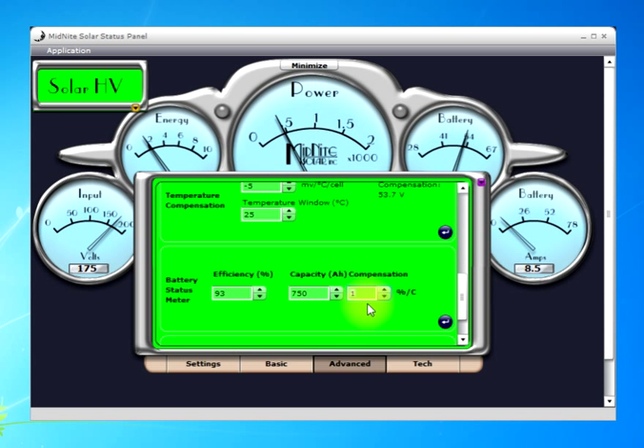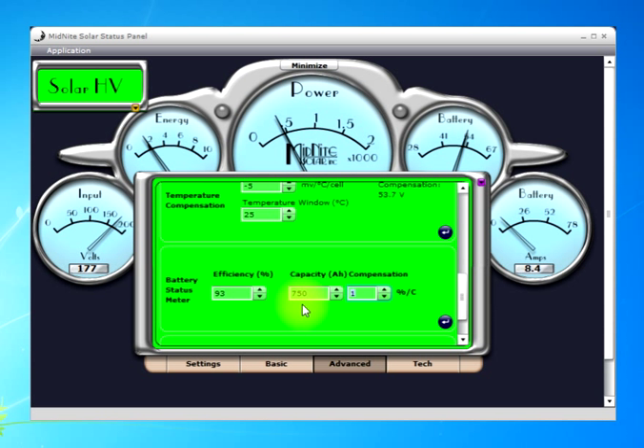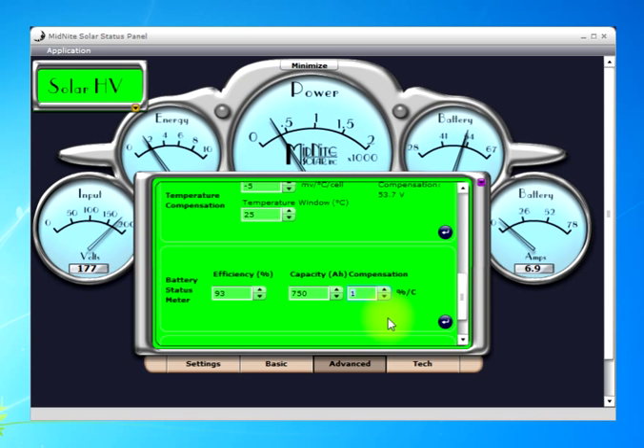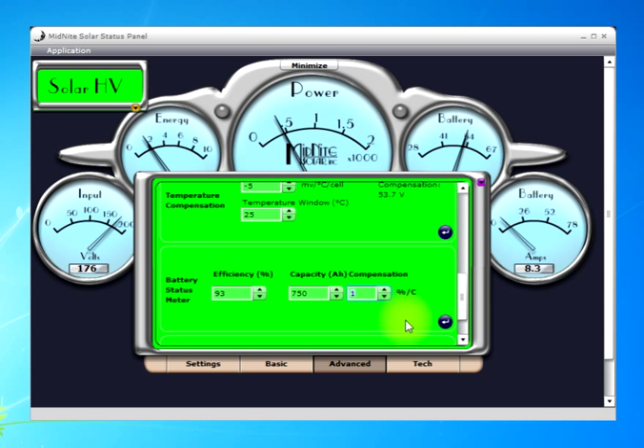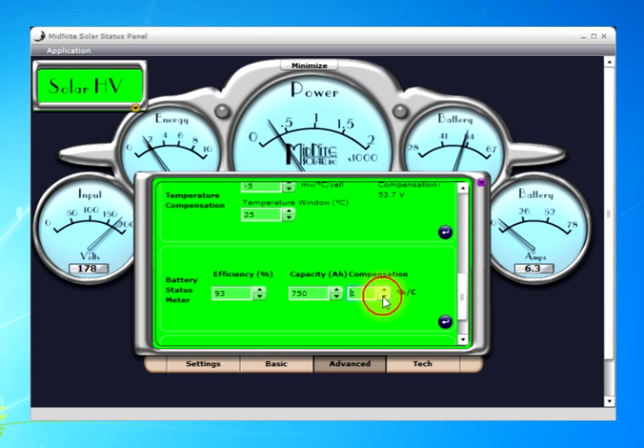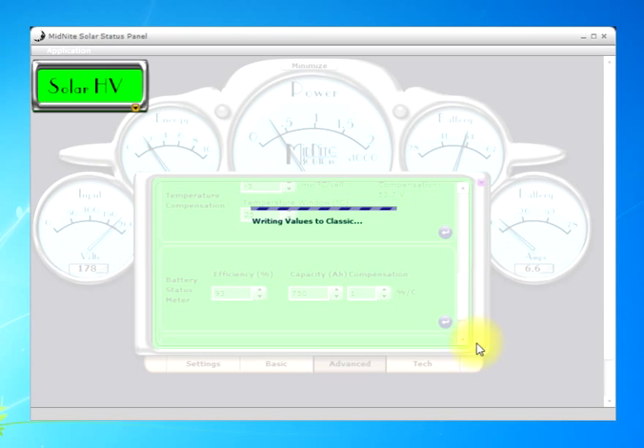This one is probably the more confusing one — it's the percent per degree C compensation for the capacity. Basically, at 25 degrees C my battery bank has 750 amp hours. But if it drops to 15 degrees C, I lose 10% — with 1% per degree C, that's 75 amp hours lost. That's not a permanent drop, just temperature-related. It also works the other way: at 35 degrees C, I gain 75 amp hours. This 1% is typically the default that most battery manufacturers want, but you can adjust it in tenths of a percent increments. Once all three values are set, commit them to the Classic.